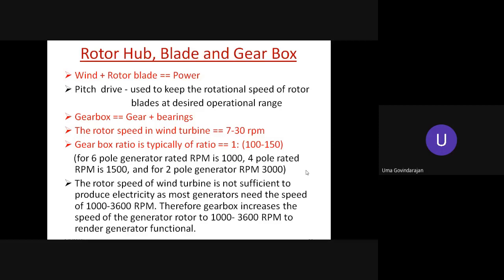The rotor speed of the wind turbine, the blades, will be rotating at a speed of 7 to 30 revolutions per minute. The gearbox steps up the speed, typically in the ratio of 1:100 to 150. That is on the mechanical side. This mechanical speed is converted into 100 to 150 times the electrical speed.